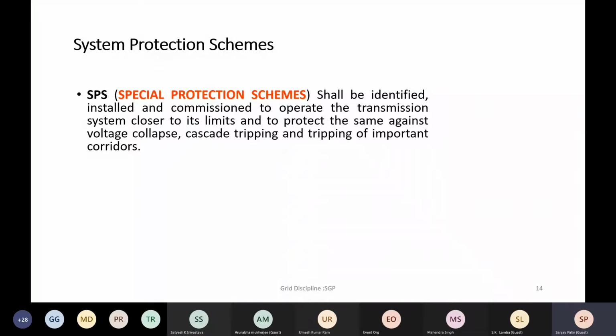So special protection schemes were recommended for taking care of certain contingencies, and we'll be discussing a little more on the special protection scheme. But one thing is that this effort has to be there, because in spite of the efforts on the generating station side, if bottlenecks are there in the transmission corridor, again it will be detrimental to the stability of the grid. So it's not that the generating station alone can play a part. The transmission also needs to provide the required control scheme.